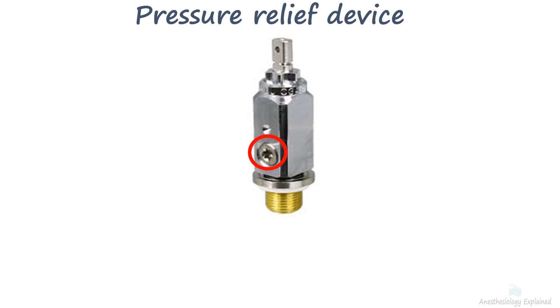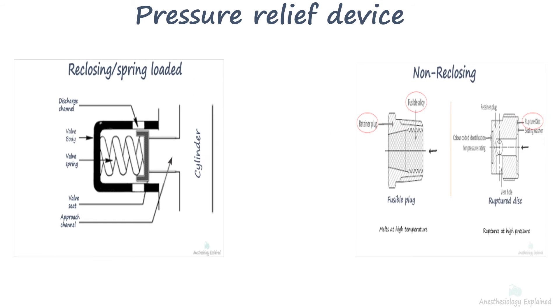Pressure relief devices are installed on cylinders with the aim of venting the cylinder contents to the atmosphere in case the pressure within the cylinder reaches a dangerous level, often due to elevated temperatures or overfilling. There are two types of pressure relief devices: reclosing and non-reclosing.